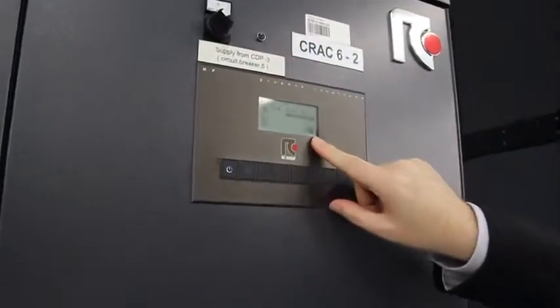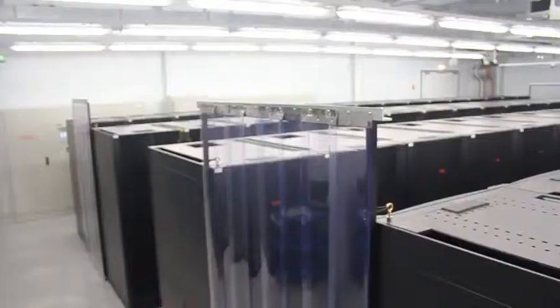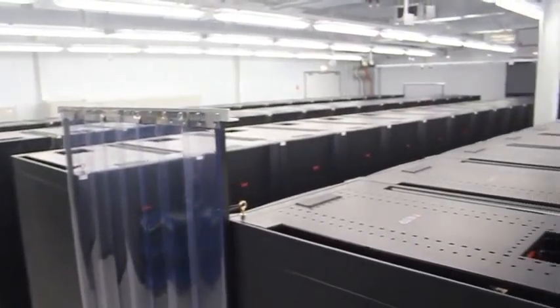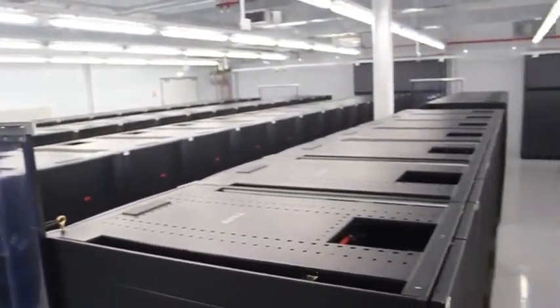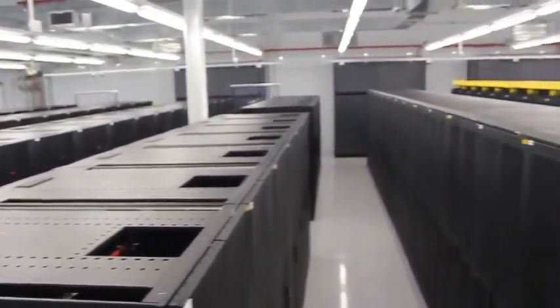As you can see, a lot of time is spent on managing the raised floor. We do everything we can to ensure that the cold air is delivered only to the front of the racks and to stop recirculation. If you note here, you can see the curtains that we've installed at the end of aisle and that all of the blanking plates are installed, and we've even put magnetic strips at the bottom of the rack to ensure as much cold air as we can deliver is delivered to the front of the servers.